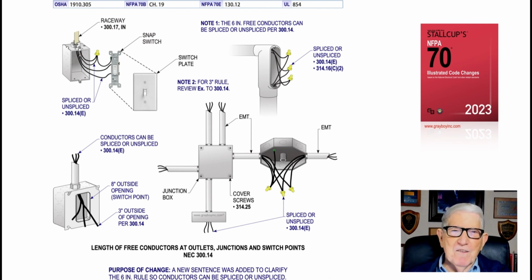To make your splices. And the same thing with the octagon box that you see at the bottom, or square box, whatever. They don't want an electrician to cut the conductor so short that they have trouble making terminations and servicing a splice that is made by an electrician. So that's what this illustration is illustrating to the user of the NEC. Make sure you have 6 inches, either measured from the back, or 3 inches measured from the front, which basically will give you enough conductor length to perform your installation.